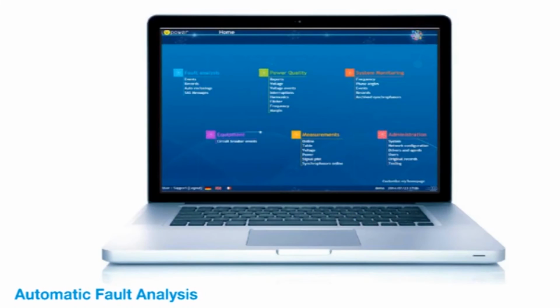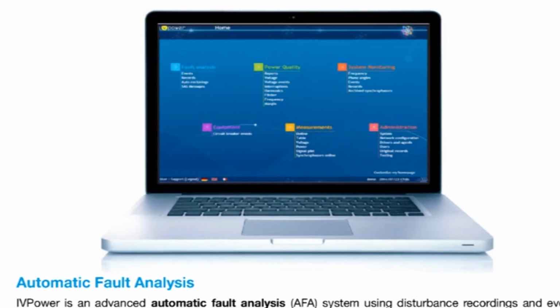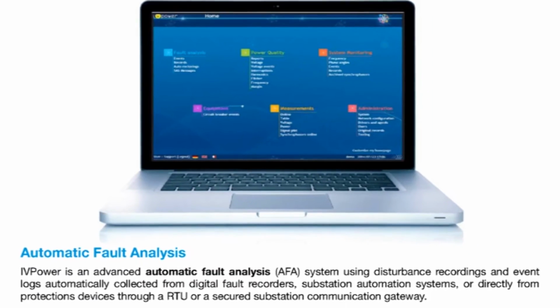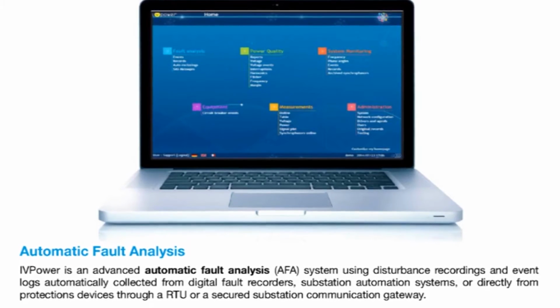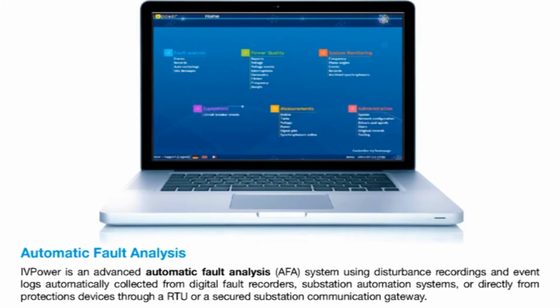the fault location equations. It's just that we have tried to make this model as sophisticated as we could in order to model correctly complex line topologies that exist, like for example 3 or 4 terminal lines or lines with shunt reactors or series capacitors and that kind of things. So once the line is modeled and once we have the COMTRADE files, either from one end or several ends, we can launch the appropriate algorithm that makes the computation.